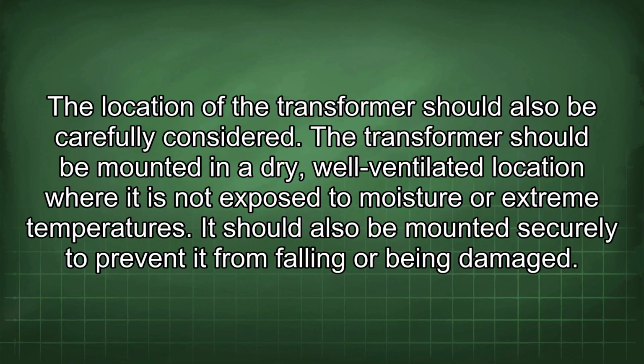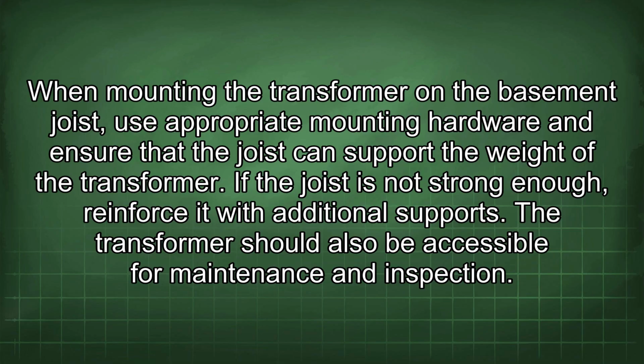The location of the transformer should also be carefully considered. The transformer should be mounted in a dry, well-ventilated location where it is not exposed to moisture or extreme temperatures. It should also be mounted securely to prevent it from falling or being damaged. When mounting the transformer on the basement joist, use appropriate mounting hardware and ensure that the joist can support the weight of the transformer. If the joist is not strong enough, reinforce it with additional supports.